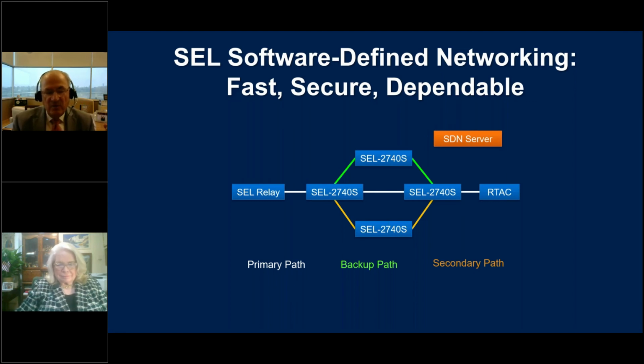First, it's non-deterministic—you can't tell what the delays are or what the routings are through the network. Second is the cyber risk—oftentimes the bad guys know the network better than the good guys. Third, when something happens in a network, it can take a long time to reconfigure itself, heal, and be back up communicating. That's the last thing you want when there's an electrical fault.